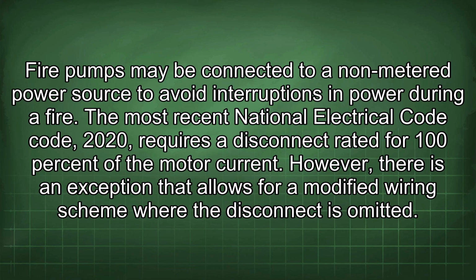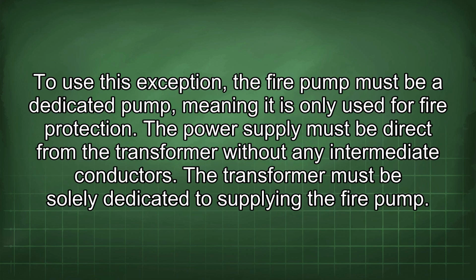The most recent National Electrical Code 2020 requires a disconnect rated for 100% of the motor current. However, there is an exception that allows for a modified wiring scheme where the disconnect is omitted. To use this exception, the fire pump must be a dedicated pump, meaning it is only used for fire protection. The power supply must be direct from the transformer without any intermediate conductors. The transformer must be solely dedicated to supplying the fire pump.